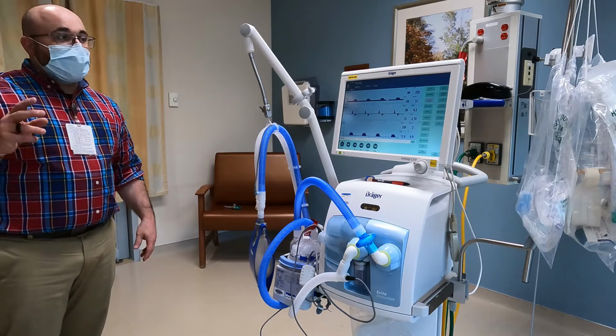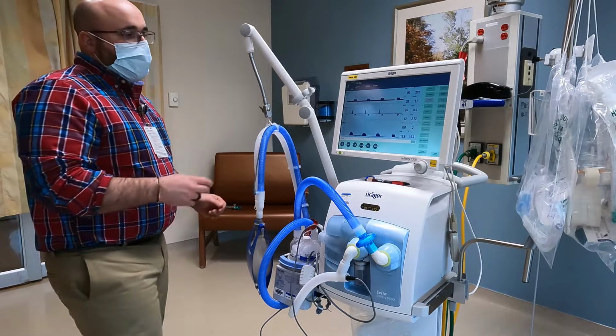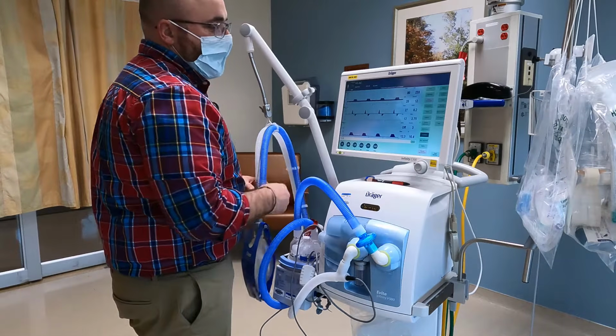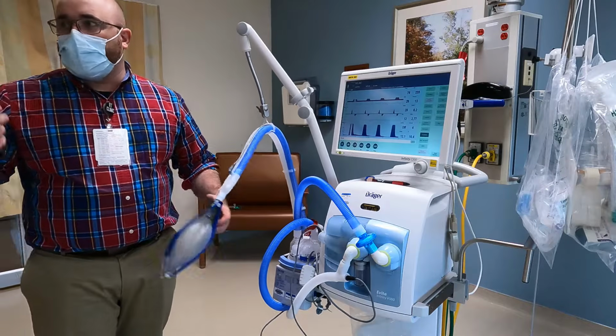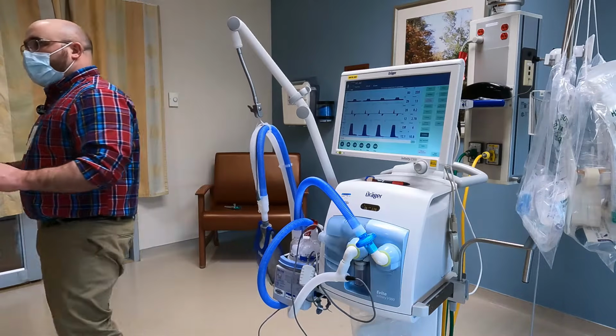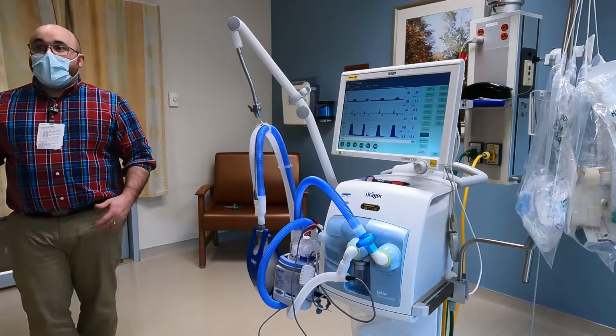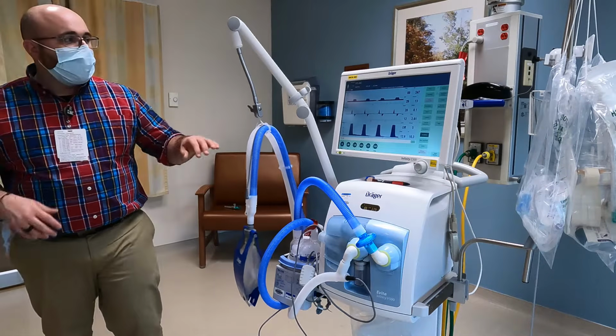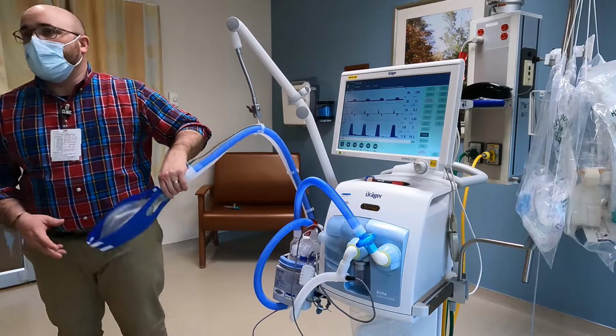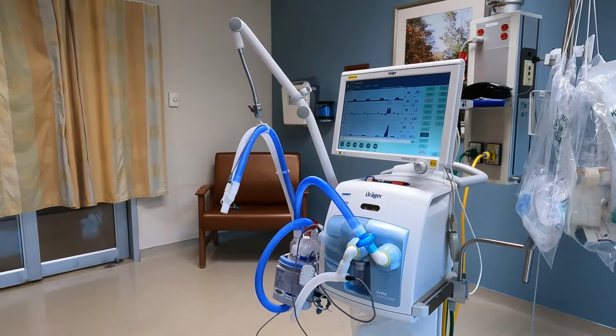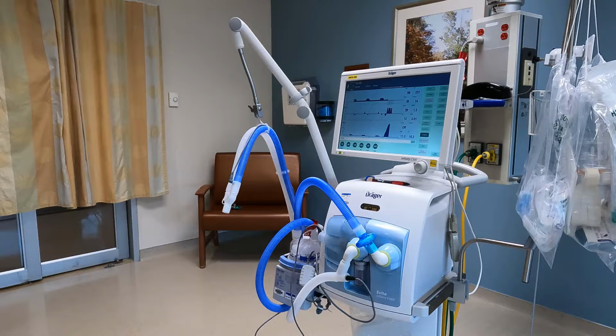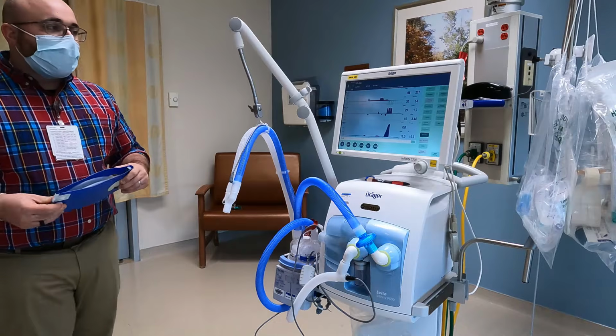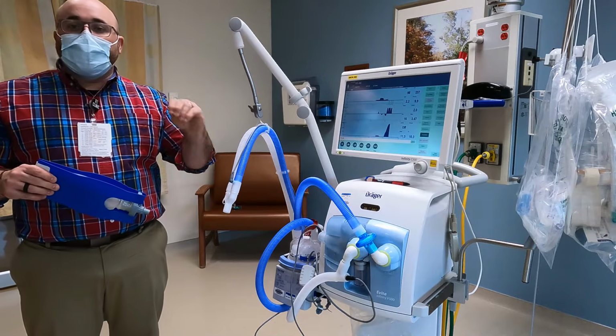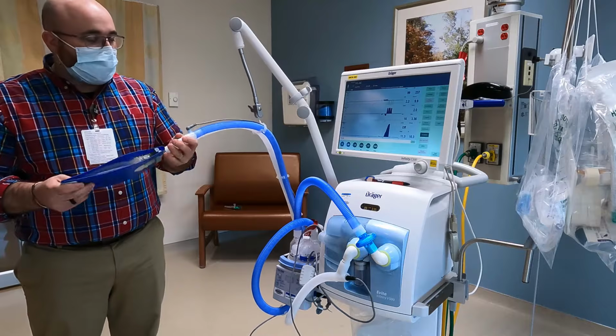So say a nurse was getting ready to suction her patient. And you go to suction your patient and then you get called for a code and you leave right now. Bad news, because what you're doing is telling your ventilator, I'm getting ready to suction, and it has 180 seconds. So if you leave and the patient coughs and pops off, it's not alarming. The next alarm you'll get will be from the monitor when they desat or something. So if you're going to hit that button, make sure that when you're finished, you cancel it. I'll show you that real quick.